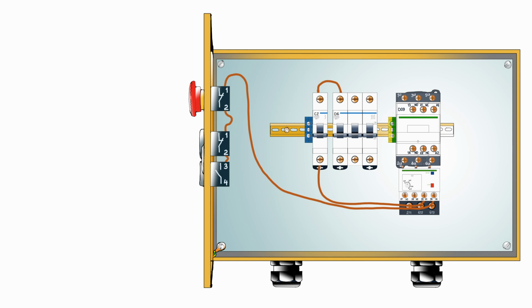So we connect a cable from 3 which goes back to our contactor, and we connect it to 13. And then from the bottom of our start button at 4, we connect another long cable that goes back to our contactor, and we connect it to 14. So this point here, 14, is also the same point with the contactor coil, which can be A1 or A2. So I would say just connect it to the one that's most convenient. 14, we connect it to the contactor coil, and the remaining point on the contactor coil, we connect it to our neutral, and that's it for our control circuit.